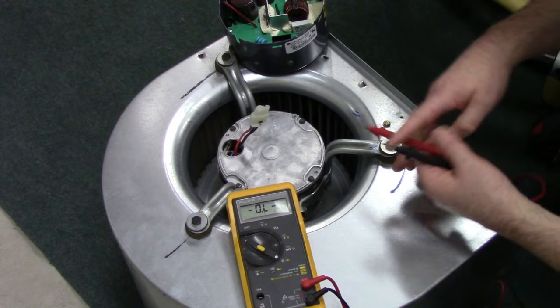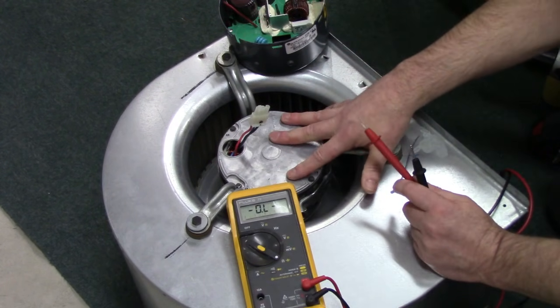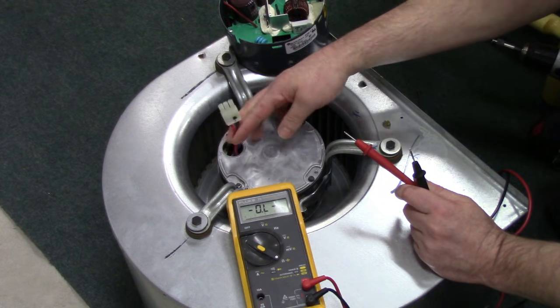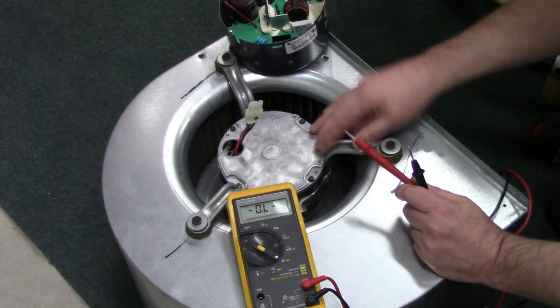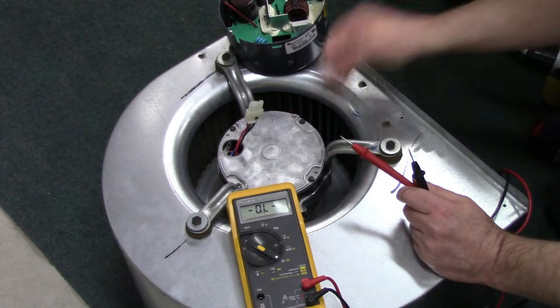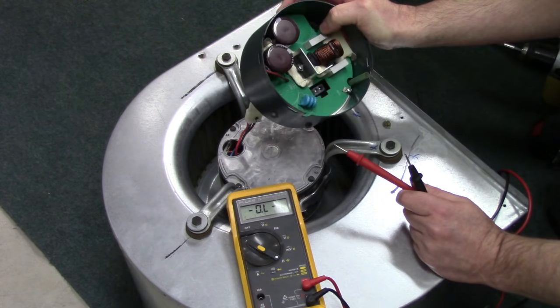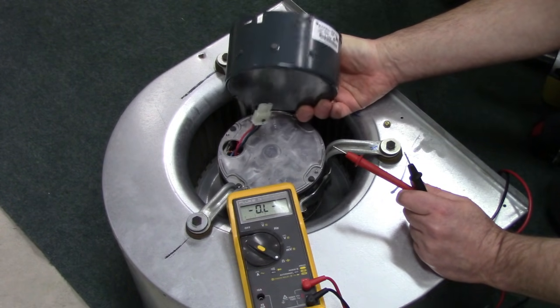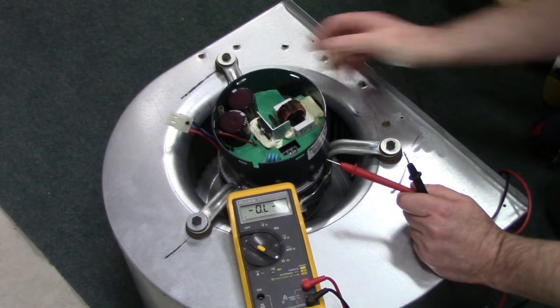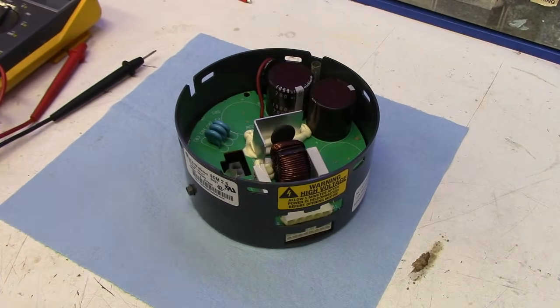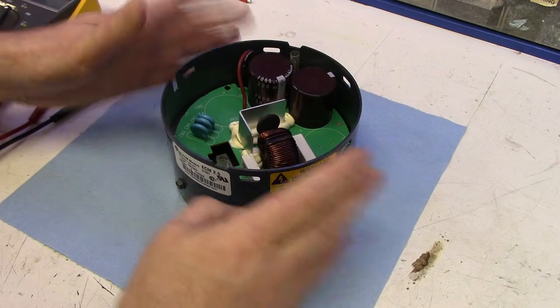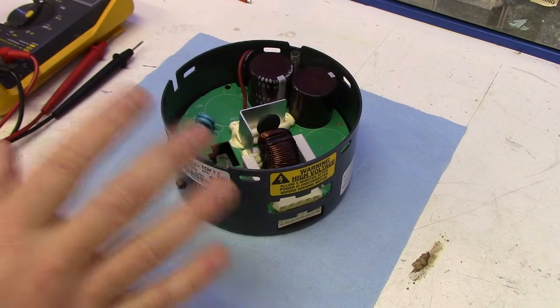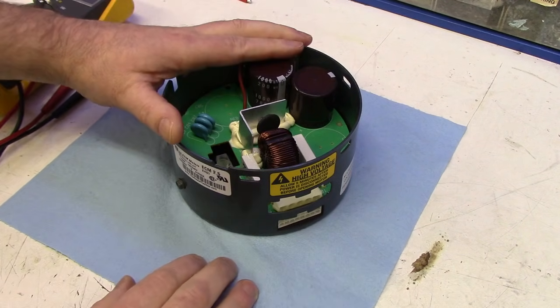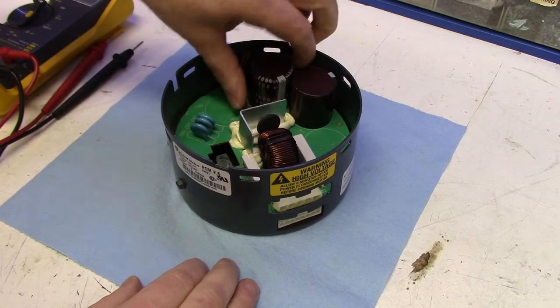They're all bang on. So the coils aren't shorted to the motor, they're not open or have a higher resistance. So we know the motor's good, so we have to start suspecting our ECM here. So we'll go to the bench and start checking that out. Okay, now that we've got the ECM out of the motor, I thought we'd just take it to the bench and show you. There's a few things that you can actually check on these.